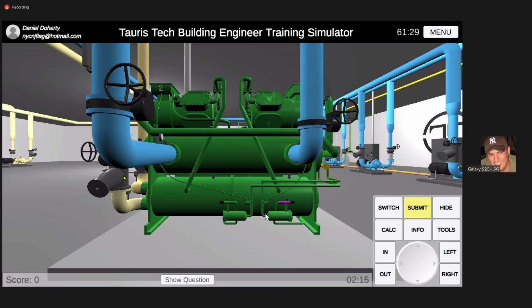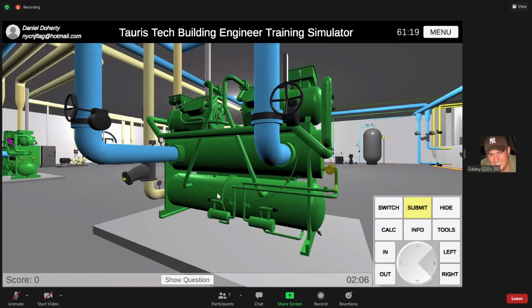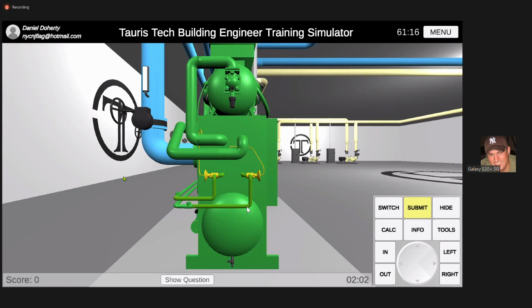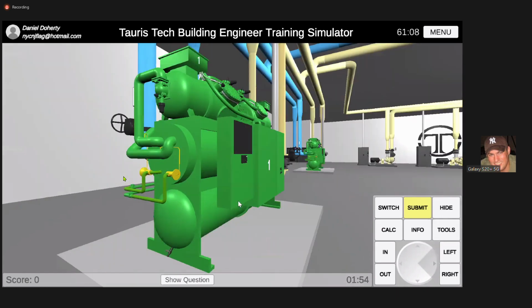What it's doing in the refrigeration cycle right now: liquid line, it's still high pressure, still high temperature, but now it's liquid. Subcooled liquid. That travels through the sight glass, all the way up the liquid line, and then it goes to your TXV. So the TXV is a midpoint. If you cut the refrigeration cycle in half, you guys know that there's a high side and a low side, right? Yeah. So your TXV is what determines the high side and the low side.